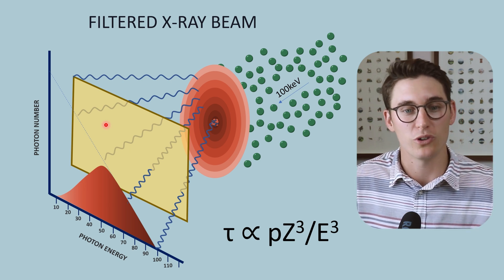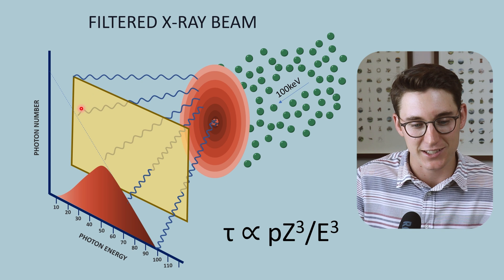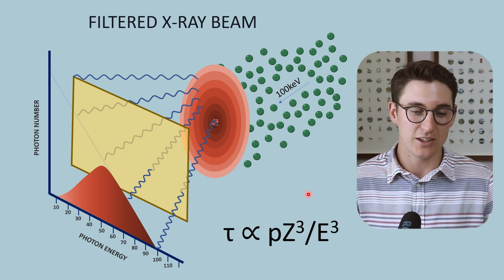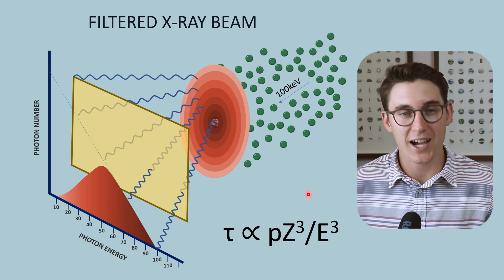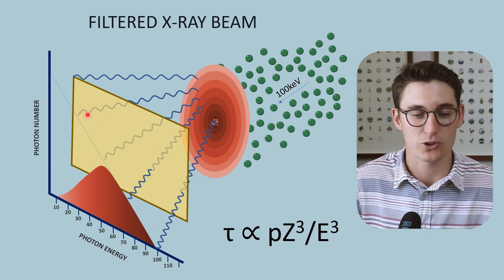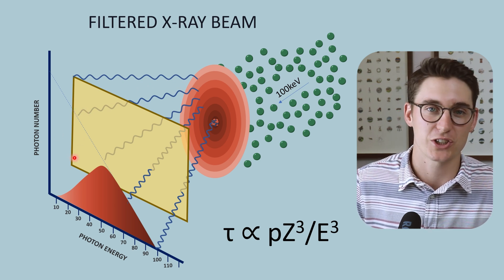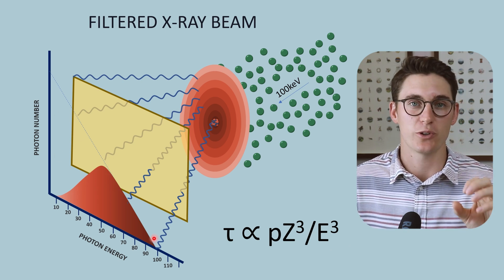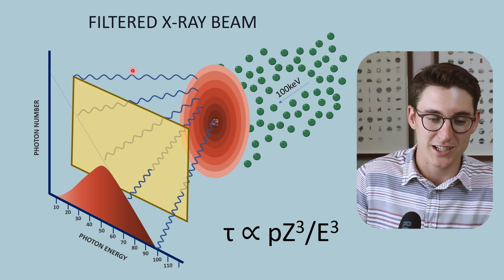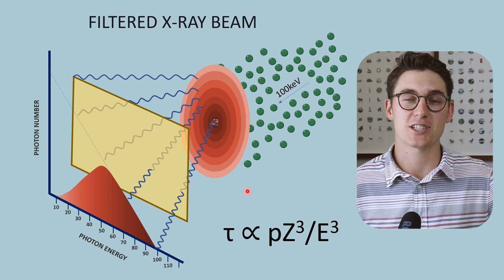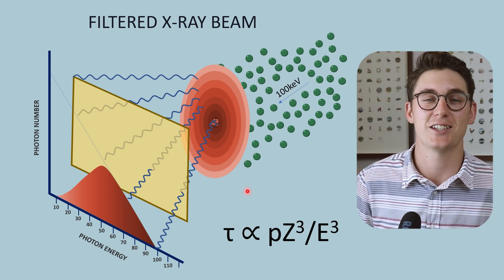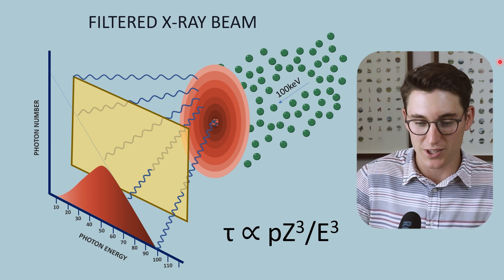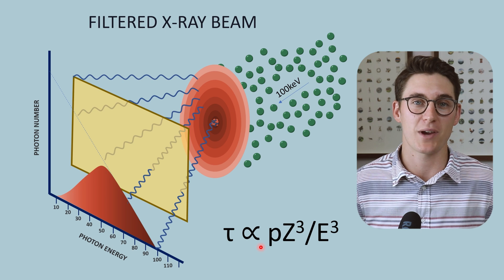Filtration is the process of removal of x-rays from an x-ray beam, preferentially removing lower energy x-rays because of the photoelectric effect. The photoelectric effect attenuates x-rays by absorbing the entire x-ray energy and releasing a photoelectron — that x-ray is completely absorbed and won't reach our patient. Because lower energy x-rays are preferentially absorbed, the higher energy x-rays continue towards our patient. This is the filtered Bremsstrahlung x-ray spectrum, a conceptual framework we will build on throughout the course.